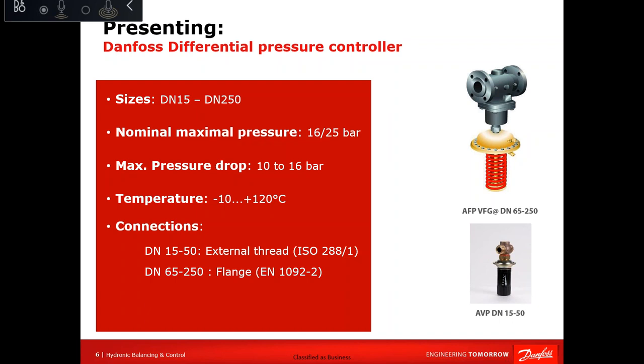But if you are telling me, because here when we presented this DPCV, we presented it for shell and core shopping malls, if you tell me that the tenant guaranteed 100% will be using a PICV matching your system requirement as pump head and flow, then fine. That is for sure okay. But till today, this is not happening. The tenant is a tenant. He will bring the cheapest and something that you as a consultant will not be the one approving it, because this tenant will be paying you money.